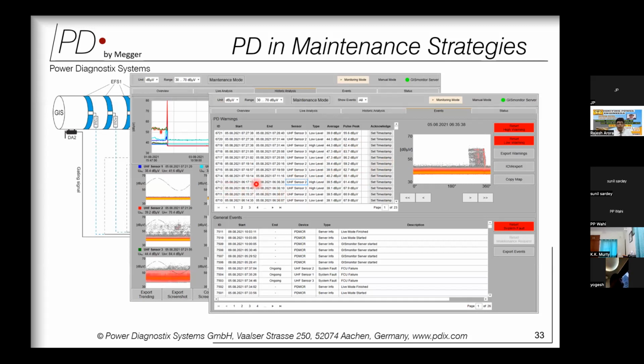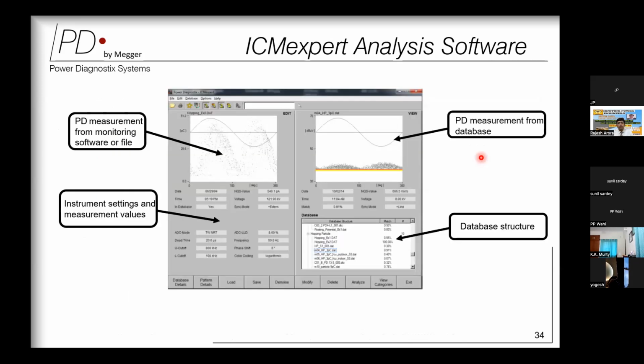Like if we see here for a particular UHF sensor, if we click on alarm, a particular PRPD pattern will be shown to you. So the benefit is that you can leave a portable instrument unattended on site, which will do recording, raise alarms and generate all the required inputs, so that it can be a completely unattended system like your online monitoring. Yet it is flexible enough that you can carry it to different assets and keep them on monitoring whenever you are in doubt about particular sensors.